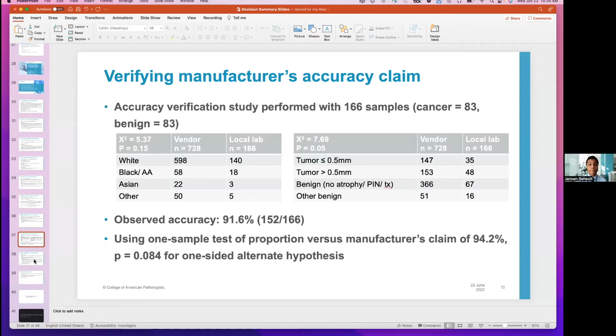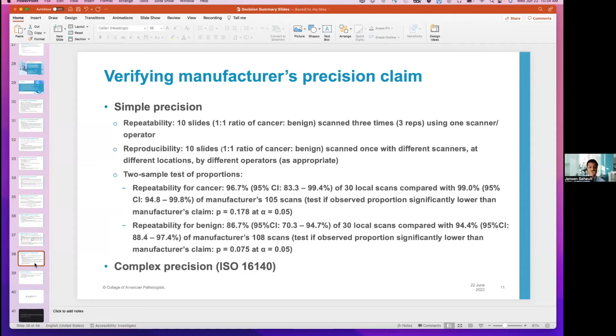Next slide. You could design a similar simple precision study where you take 10 slides and scan them 3 times using one scanner operator, or a reproducibility study using 10 slides scanned once with different scanners at different locations by different operators, and compare your performance to the vendor's claim to see whether it matches. Next slide.